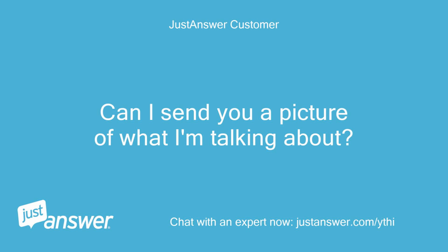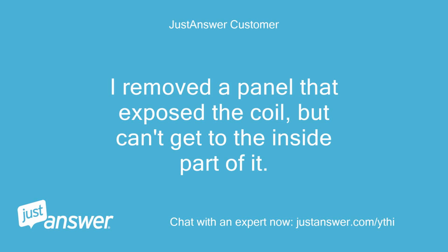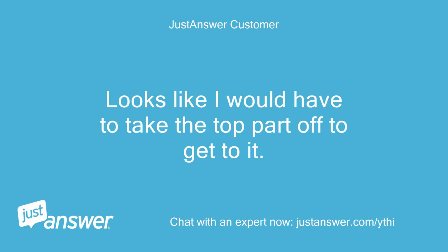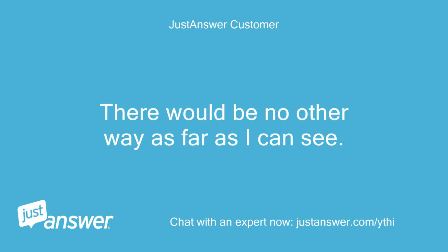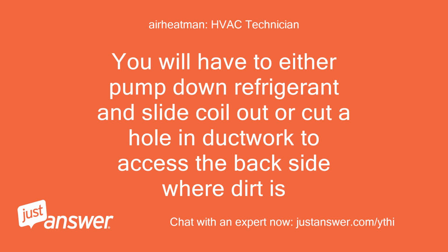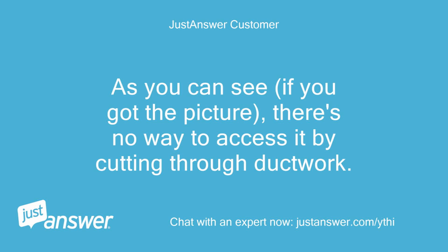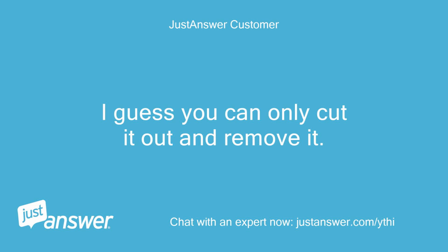Can I send you a picture of what I'm talking about? I removed a panel that exposed the coil, but can't get to the inside part of it. Looks like I would have to take the top part off to get to it. There would be no other way as far as I can see. You will have to either pump down refrigerant and slide coil out, or cut a hole in ductwork to access the back side where dirt is. As you can see, if you got the picture, there's no way to access it by cutting through ductwork. I guess you can only cut it out and remove it.